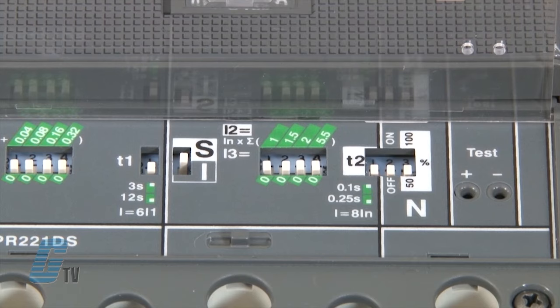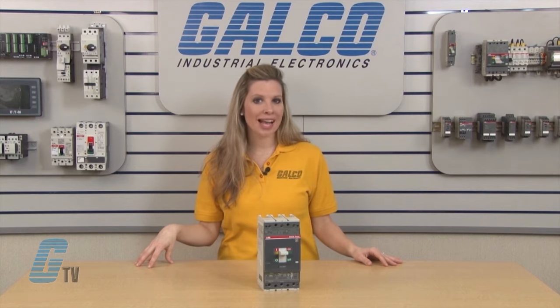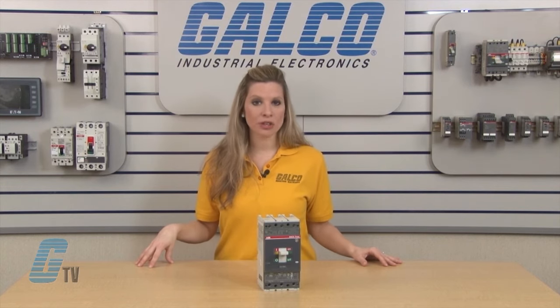The dip switches in the middle will determine the short circuit threshold. This can be from one to ten times the maximum current rating of the circuit breaker.